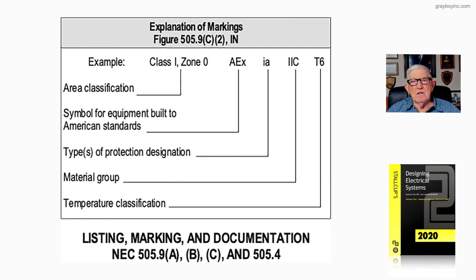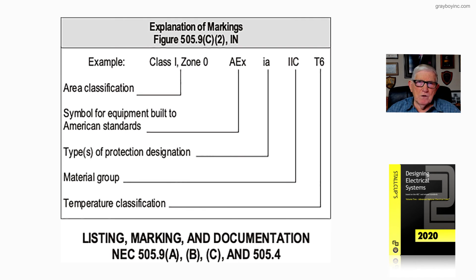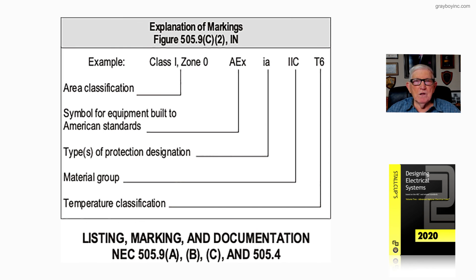Then the temperature classification is T6, so you could put it in a temperature area that falls under the table of your T-code letters, which is T6. This is the type of marking that will be on equipment manufactured in Europe, for example, showing that it meets United States standards so the authority having jurisdiction can look at NEC 110.3b and c and approve the equipment by 500.8a. That's what illustration 21-69 is showing the user of the NEC.